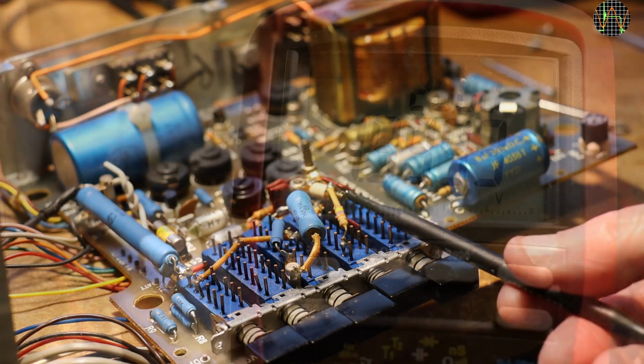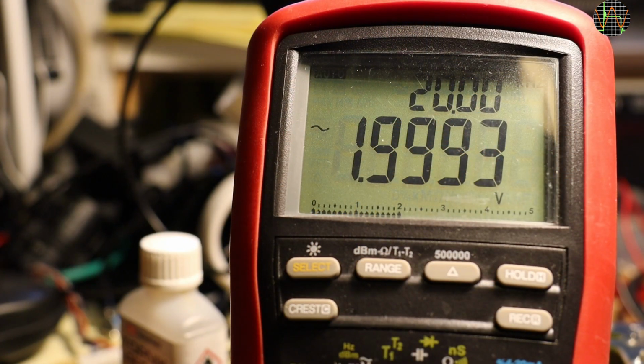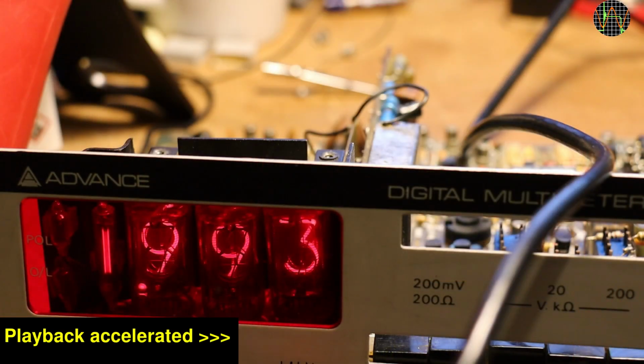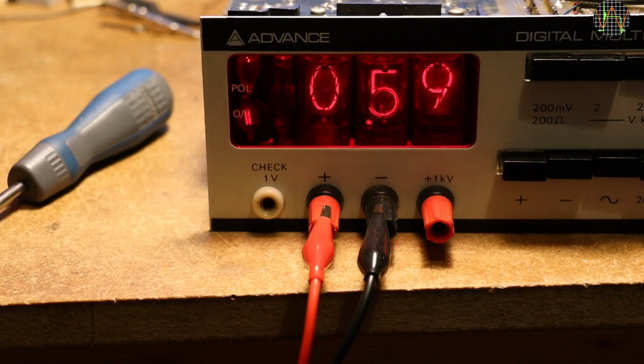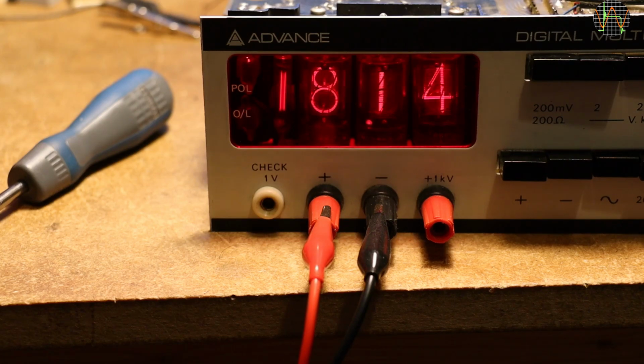Now that you see how this is done, the 2 volts HF calibration. This uses 1.999 volts at 20 kHz. As this trimmer is easily accessible in the disassembled state, I can use a proper trimmer tool, but even this has a reaction by just touching the capacitor, which makes adjusting tricky. For the 20 volts HF, this is much harder because only a thin metal screwdriver will fit through the PCB and able to turn the screw. I tried all plastic tools and they either don't fit or can't produce the torque needed to turn the trimmer. The problem is that the metal screwdriver massively disturbs the capacitance and therefore the reading by just being there. The only way is to adjust blindly, then remove the screwdriver, see what the display settles on and then try again until it's close enough.